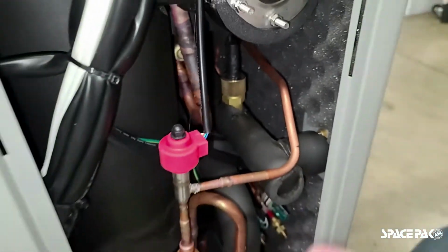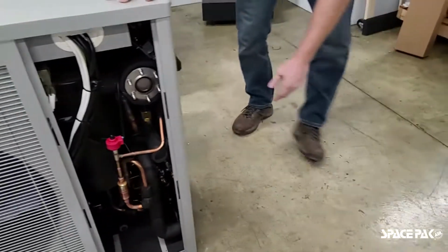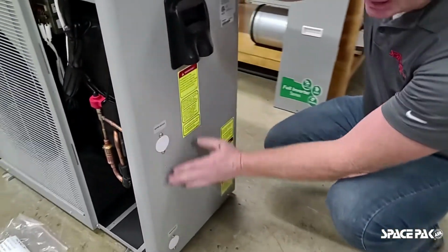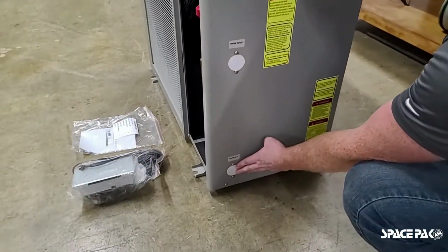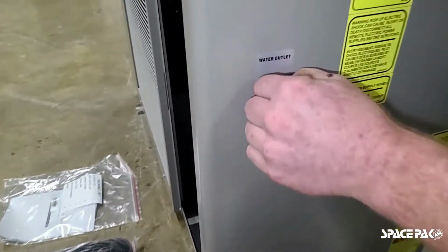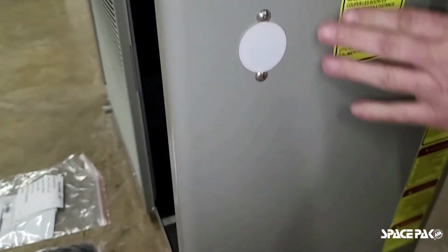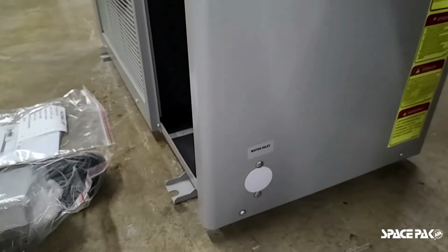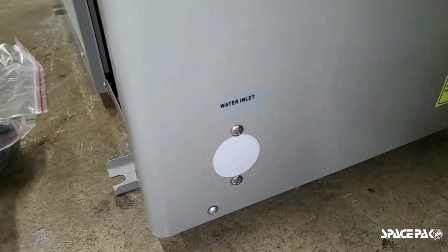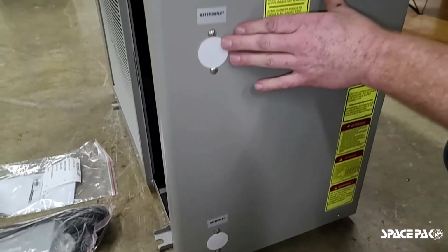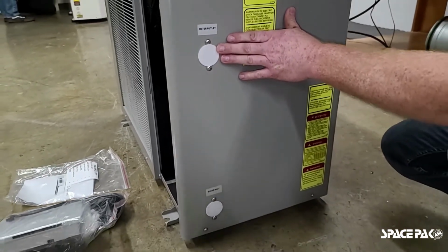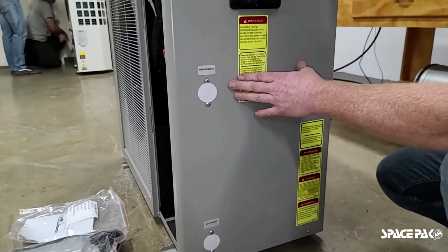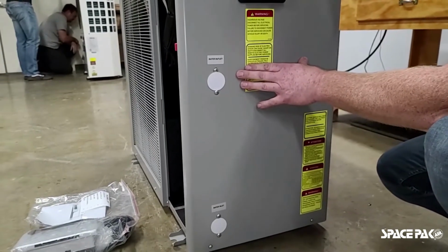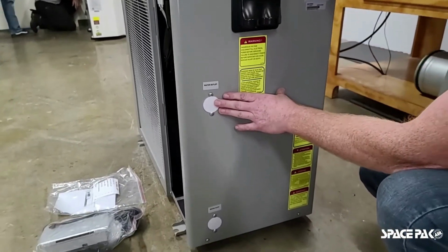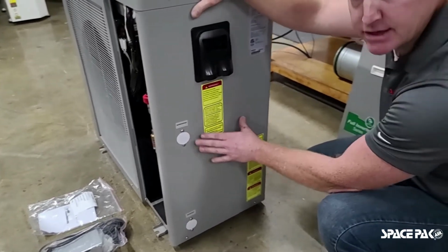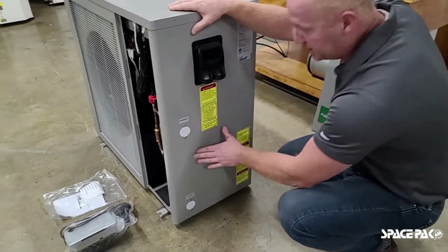Okay, if we were to look around to the right side of the unit, we have our inlet and outlet water tappings. They come with little plugs, dust covers to keep anything out. We know now that the water inlet is on the bottom and the water outlet is on the top. These are 1-inch female thread tappings. The next size up in this series, the 060 series, the 5-ton, will have 1.25 inch tappings, where this one currently has the 1-inch tappings.